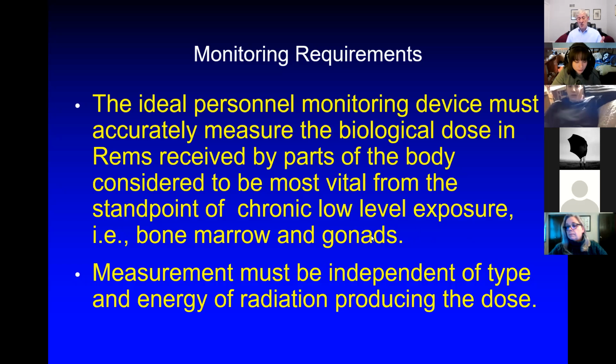So, I see people wearing their film badges in the wrong place. You may have seen people wearing it up on their collar. Last time I looked, nobody's bone marrow is up there. Your bone marrow is in your pelvis. It's not up there. So wearing it up there is not doing any good. It's not assessing anything directly related to gonadal or bone marrow dose. And that's number one. We want to put it in the right place. We want to measure the dose to those critical organs.